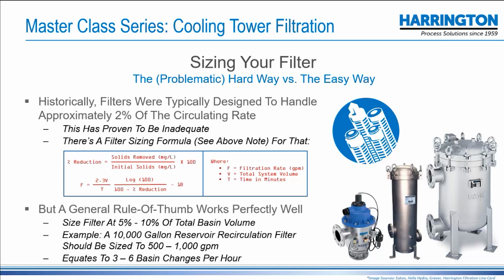It's totally inadequate. The best general rule of thumb I mentioned earlier is 5% to 10% of the total basin volume. As in the example I gave, 10,000 gallons would equate to 500 to 1,000 GPM. That also equates to about 3 to 6 basin changeouts per hour. When you think of air conditioning in a room, the major consideration is how many times we exchange the air within the room. And that'll give you a number of efficiencies. So I would highly recommend, as the best rule of thumb, unless there are other considerations, that we just use 5% to 10% as the best approach.